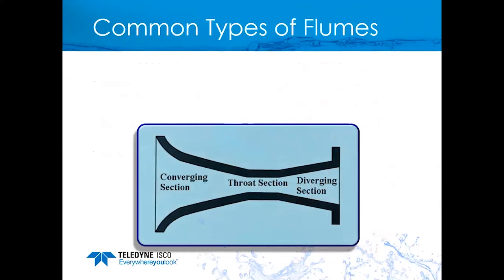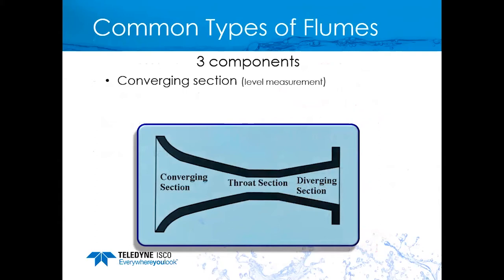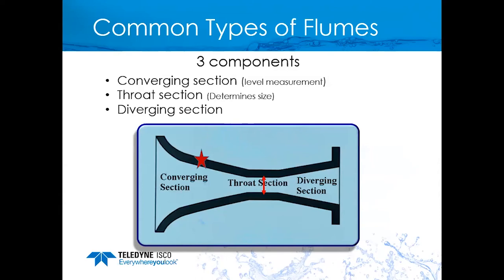The other type of primary device is a flume. The three components are the converging section — the approach side where level measurement is taken — the throat section, which determines the flume size and is measured across the narrowest part; and the diverging section where water exits. When ordering a flume, specifying your technology — bubbler, submerged probe, or ultrasonic — allows it to be built into the flume at the correct measurement point. The narrower throat accelerates water, making the flume essentially self-cleaning.